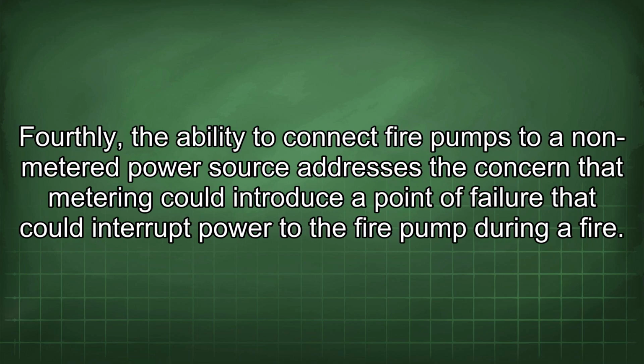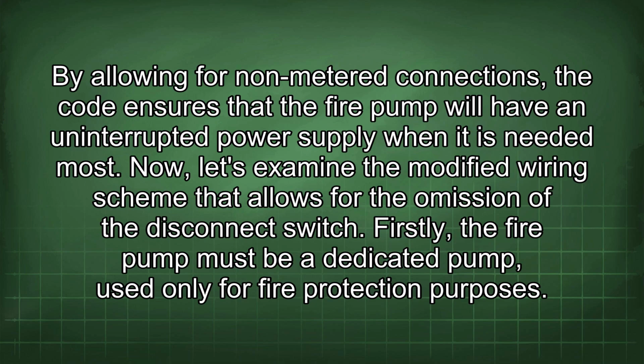Fourthly, the ability to connect fire pumps to a non-metered power source addresses the concern that metering could introduce a point of failure that could interrupt power to the fire pump during a fire. By allowing for non-metered connections, the code ensures that the fire pump will have an uninterrupted power supply when it is needed most.